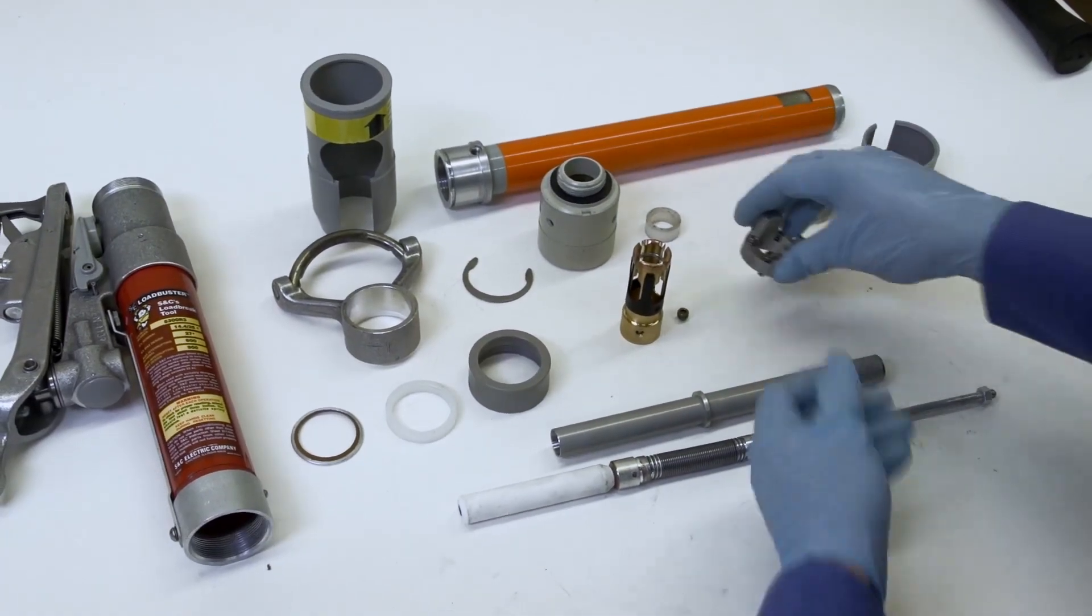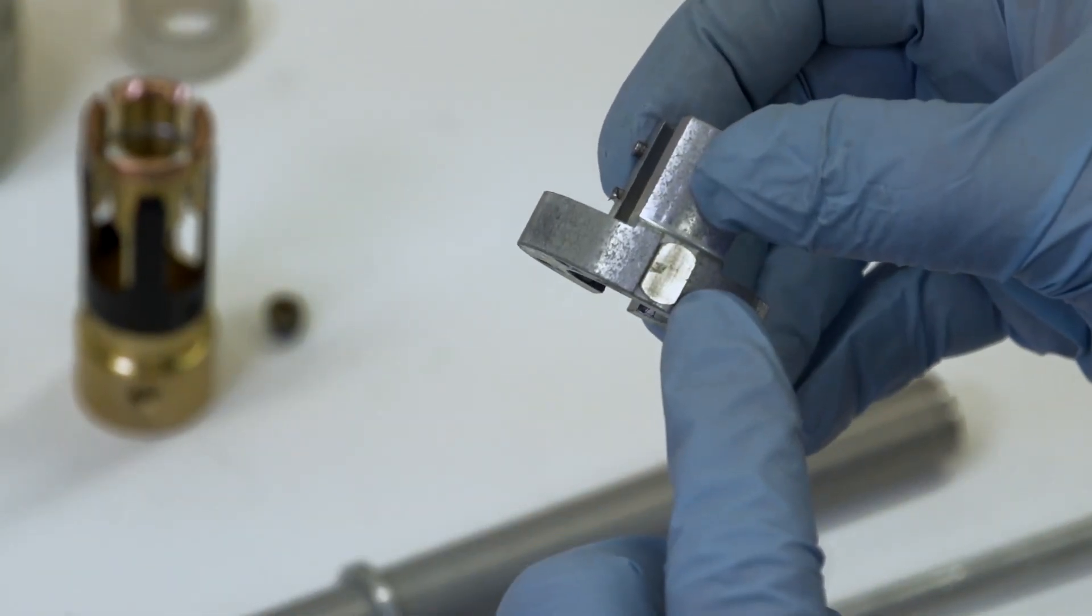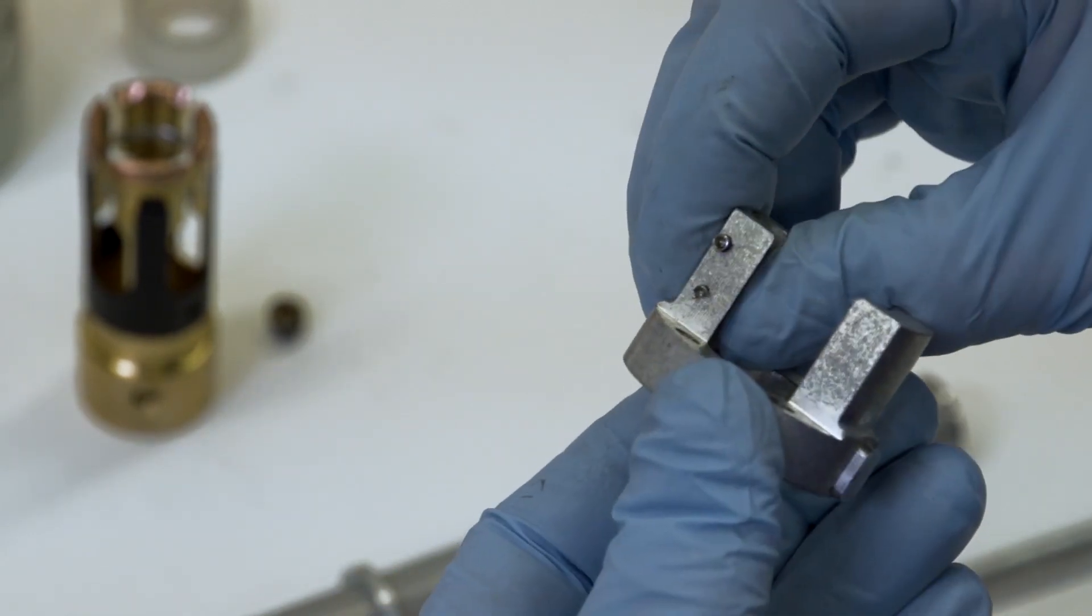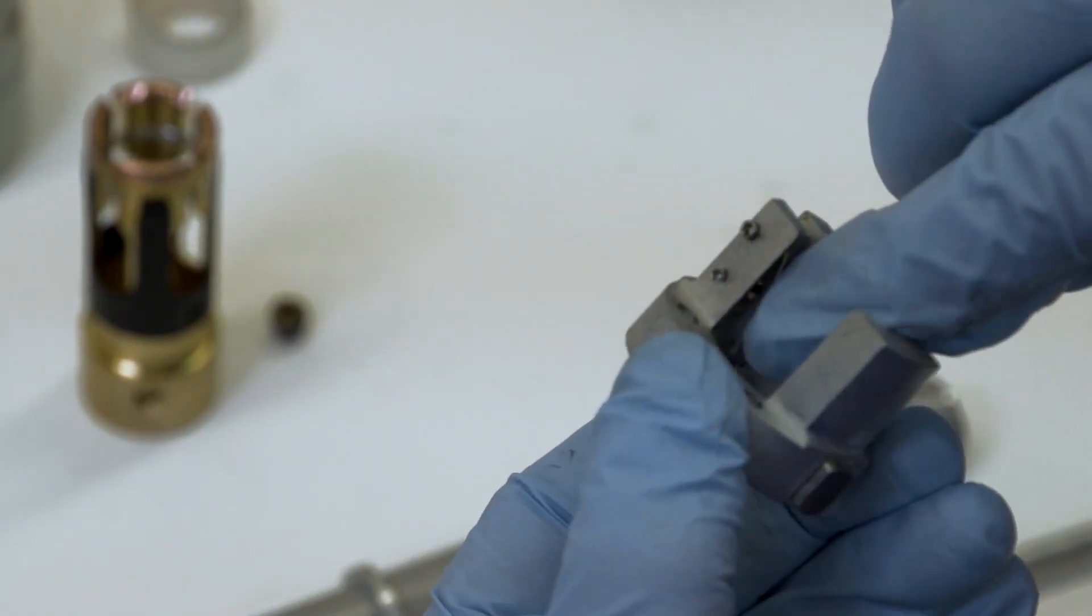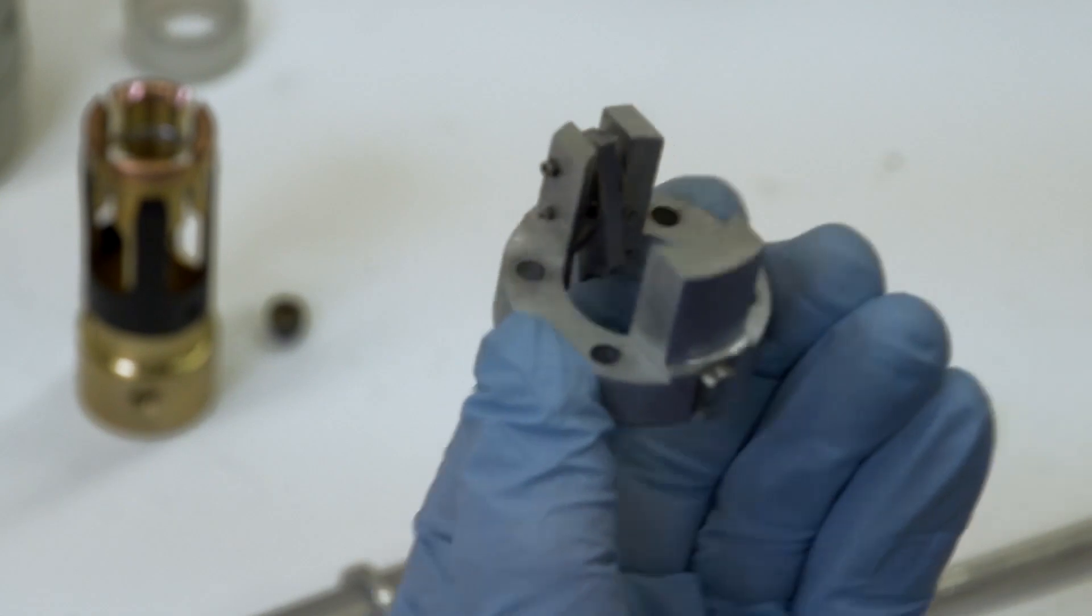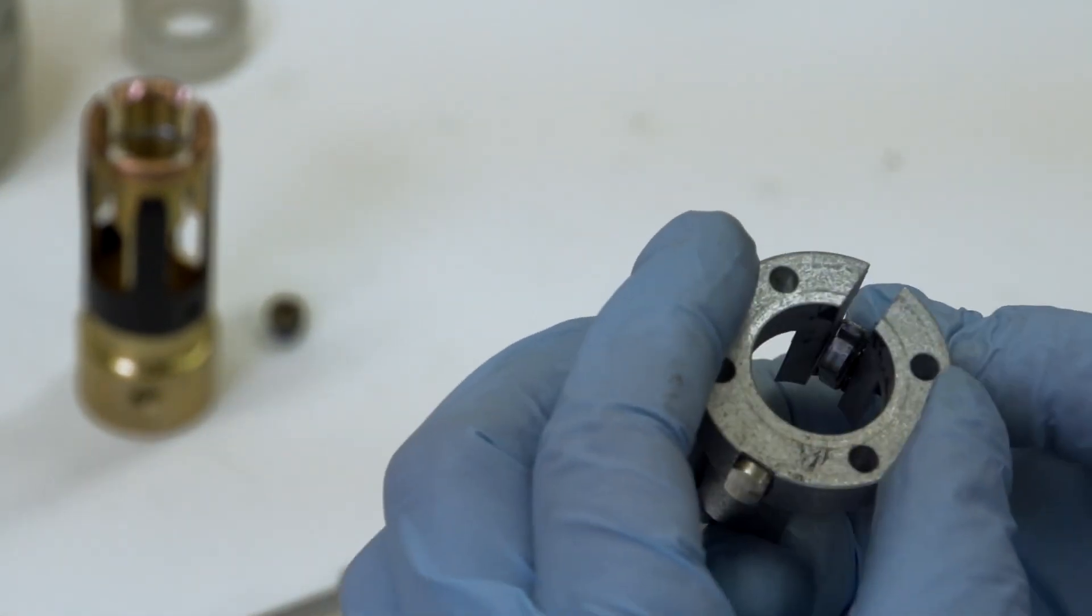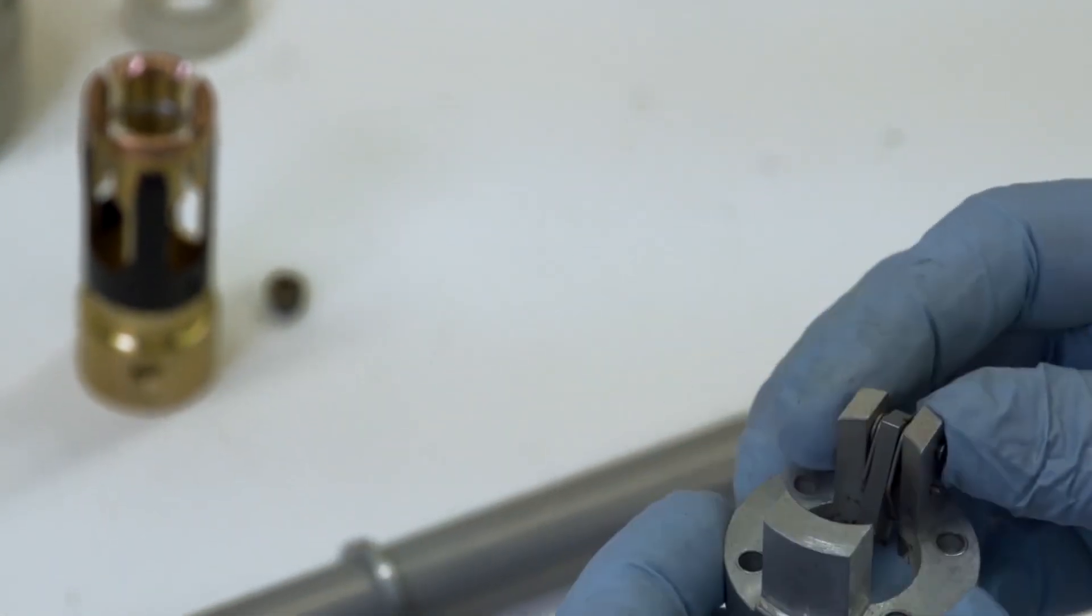Examine the trigger to make sure the spring is working and that the key is still securely in place. Look for evidence of excessive wear, broken springs, burning, or pitting of any part of the assembly. If wear is found, the entire trigger assembly should be replaced.